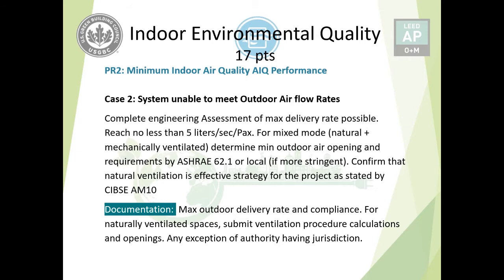In some places, due to climate conditions, natural ventilation is not an effective or feasible strategy. If using a natural ventilation mode, you must show that it is effective in the local weather and climate conditions. Documentation includes the maximum outdoor delivery rate, how the 5 liters per second is achieved, ventilation procedure calculations, and the openings — which are the only way air can be exchanged. If there are more stringent local codes, the exception from the authority having jurisdiction should also be submitted.